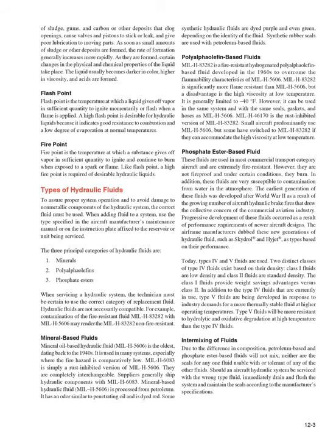As soon as small amounts of sludge or other deposits are formed, the rate of formation generally increases more rapidly. As they are formed, certain changes in the physical and chemical properties of the liquid take place. The liquid usually becomes darker in color, higher in viscosity, and acids are formed.